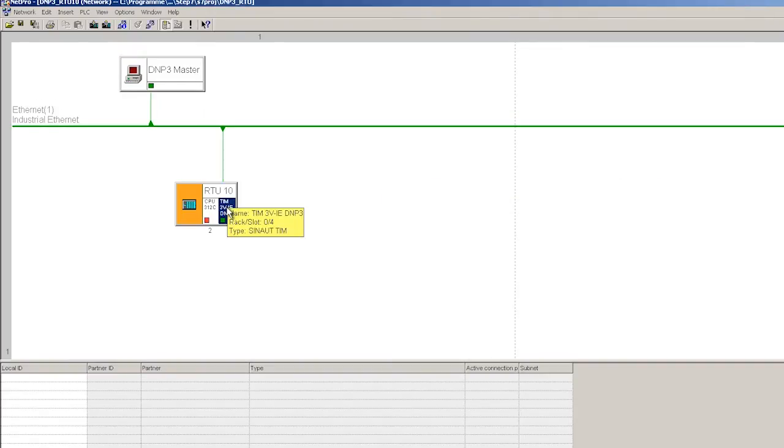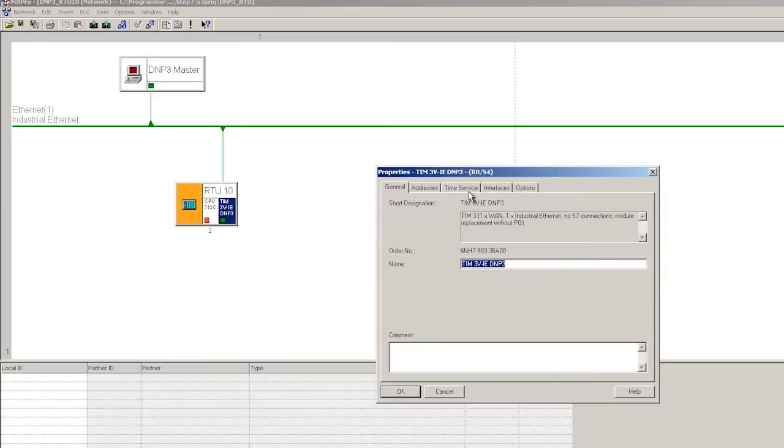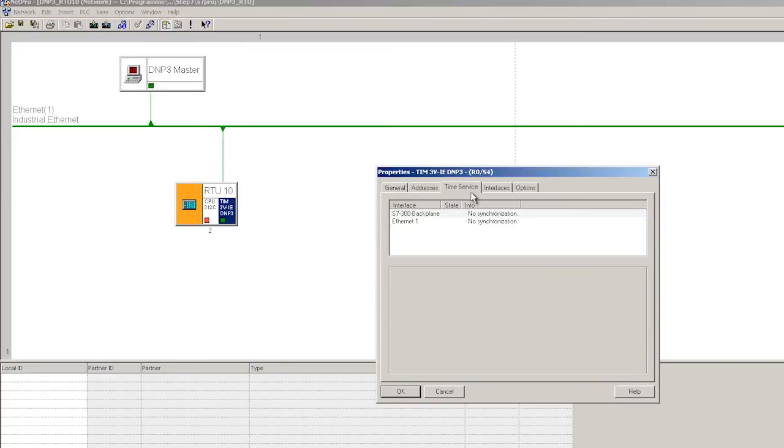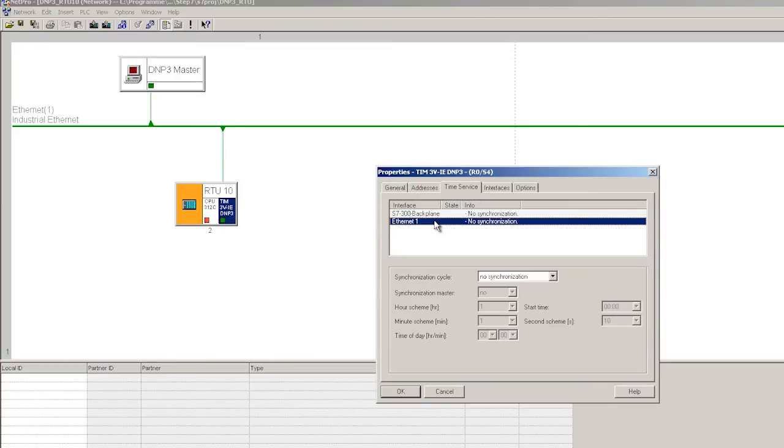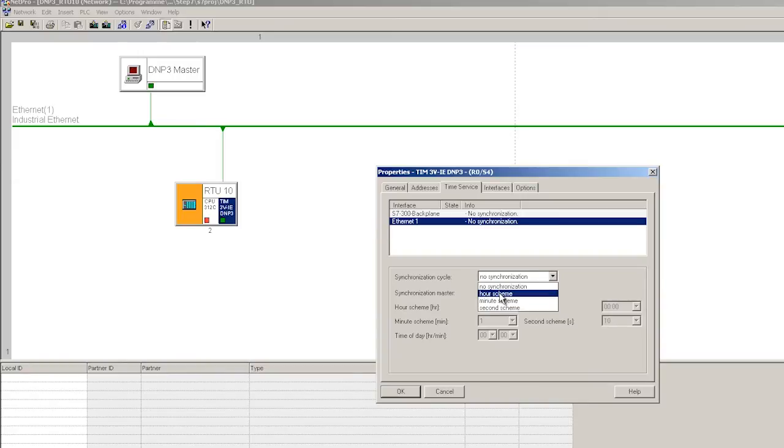In the TIM object properties we configure the time synchronization on the Time tab. The time synchronization interval is the interval at which the control center sends the time to the station. For example, here we configure a time synchronization of 2 hours.